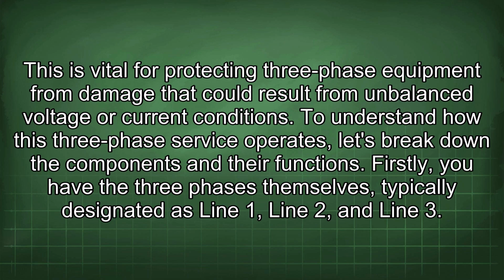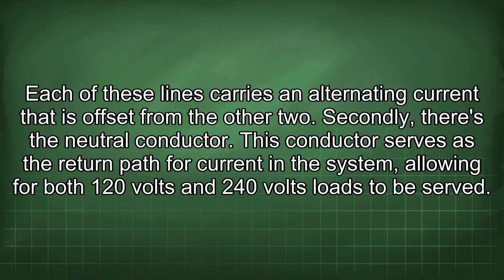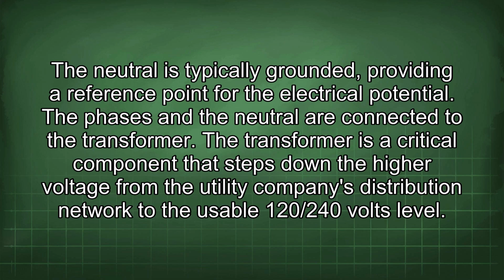To understand how this 3-phase service operates, let's break down the components and their functions. Firstly, you have the 3 phases themselves, typically designated as line 1, line 2, and line 3. Each of these lines carries an alternating current that is offset from the other 2. Secondly, there is the neutral conductor. This conductor serves as the return path for current in the system, allowing for both 120 volts and 240 volts loads to be served. The neutral is typically grounded, providing a reference point for the electrical potential.